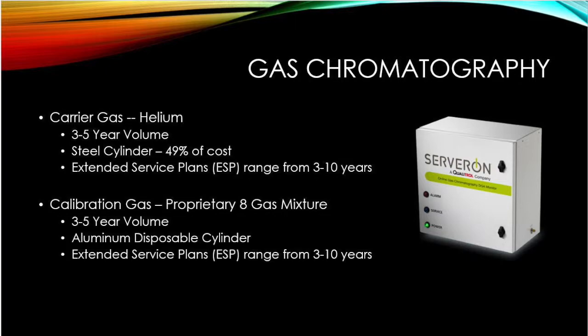Currently, the steel helium cylinders that are used for the gas chromatography units last 3 to 5 years. They contain around 8,000, almost 9,000 liters of helium, but at a standard sampling rate, that helium will last between 3 and 5 years. The steel cylinders are actually roughly 49% of the cost of the helium purchase. The rest of the cost is made up of the helium itself.